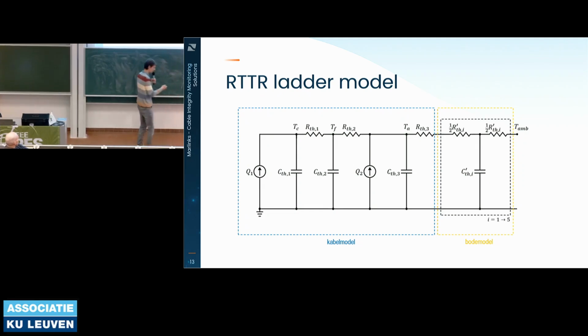IEC also made a thermal ladder model like this, but they don't have a node for the fiber. They only have a node for the core, the screen, the armor, and the ambient, and maybe one more, but not for the fiber. So you can use the IEC model to make a thermal model, but it doesn't give you the temperature at the fiber. And you cannot start calculating the core temperature if you don't know the temperature at the fiber location.